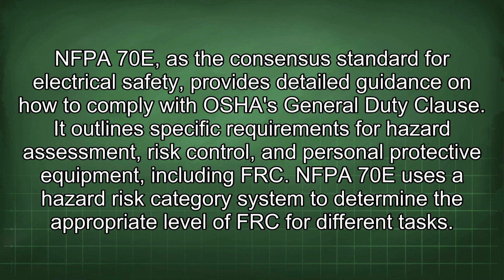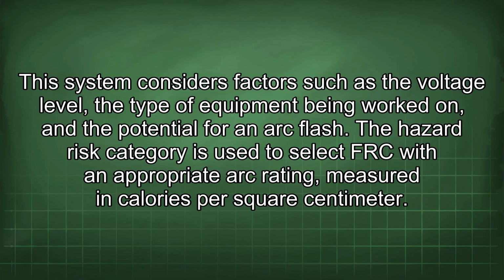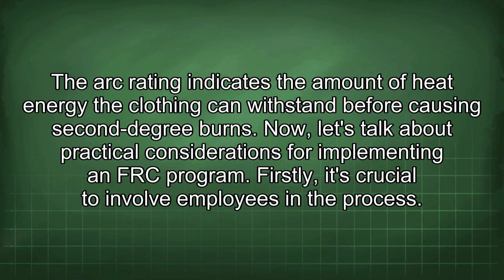NFPA 70E, as the consensus standard for electrical safety, provides detailed guidance on how to comply with OSHA's General Duty Clause. It outlines specific requirements for hazard assessment, risk control, and personal protective equipment, including FRC. NFPA 70E uses a hazard risk category system to determine the appropriate level of FRC for different tasks. This system considers factors such as the voltage level, the type of equipment being worked on, and the potential for an arc flash. The hazard risk category is used to select FRC with an appropriate arc rating, measured in calories per square centimeter. The arc rating indicates the amount of heat energy the clothing can withstand before causing second-degree burns.